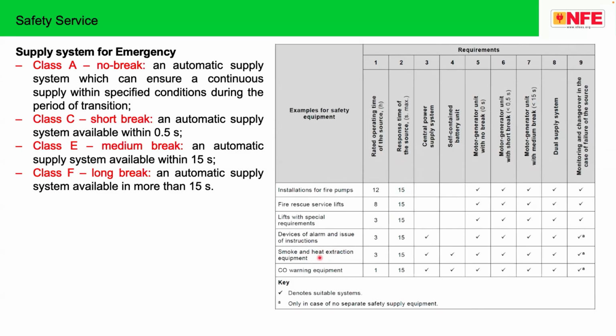Smoke and heat extraction equipment. The rated operating time of the source must be capable of providing the electricity for up to this much time, say, for example, 3 hours with 15 seconds changeover time. So now various applications and various selections are very well defined in the electrotechnical standards.